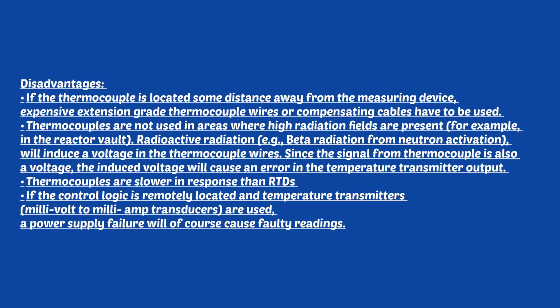in the thermocouple wires. Since the signal from a thermocouple is also a voltage, the induced voltage will cause an error in the temperature transmitter output. 3. Thermocouples are slower in response than RTDs. And 4. If the control logic is remotely located and the temperature transmitter or millivolt to milliampere transducer is used, a power supply failure will of course cause faulty reading.